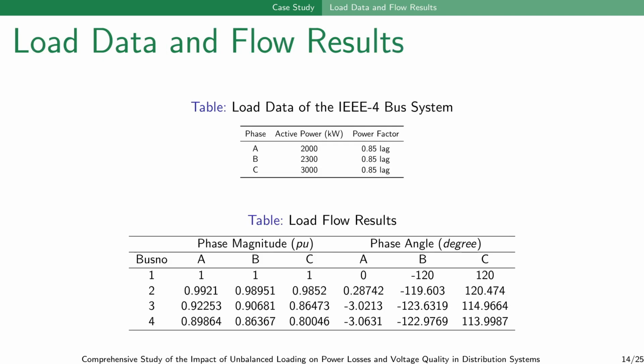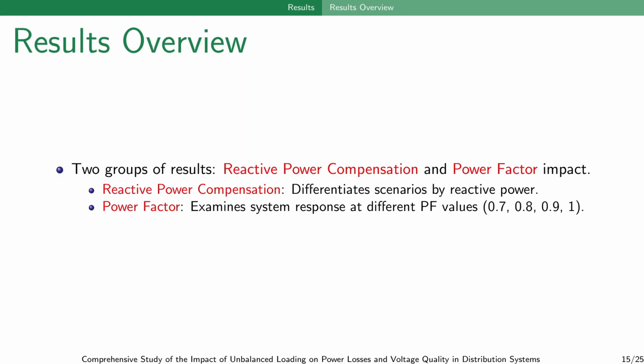The table here presents the load data for the IEEE 4-bus modified system, and the load flow results shown in the second table indicate the phase, magnitude, and angle at different buses under the given load and conditions. Let's discuss the results. In our study, we divide our results into two groups: the impact of the reactive power compensation and the power factor on the distribution system. The first group differentiates scenarios based on the reactive power, while the second group examines the system response at different power factor values.